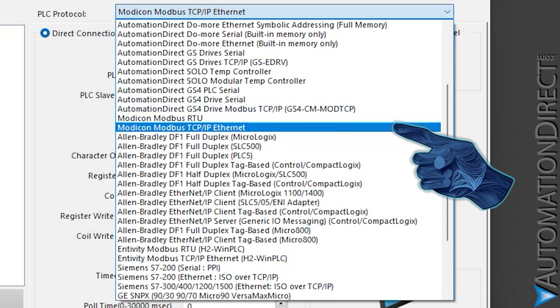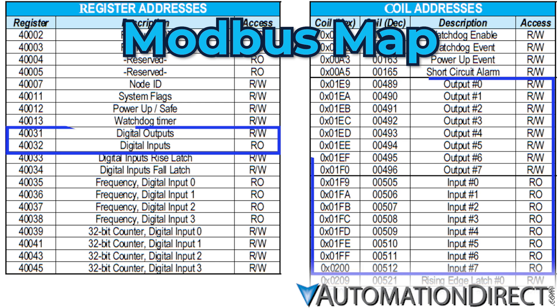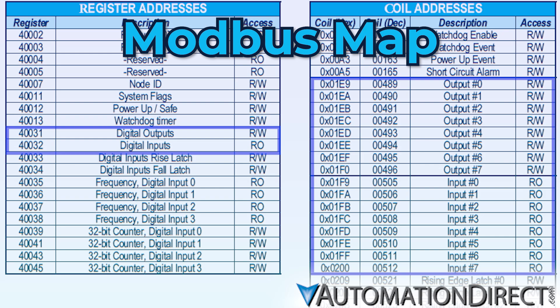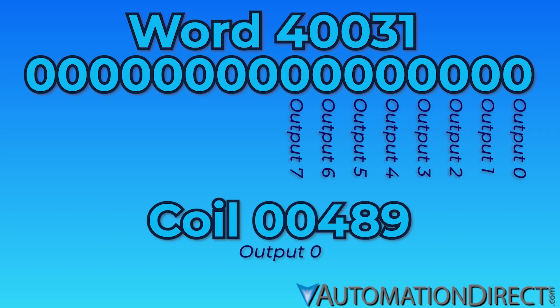Not to worry — in cases like this, we'll pick a more generic Modbus driver. We're using Modbus TCP, so we'll use the Modicon Modbus TCP/IP Ethernet selection. First, we'll set up our tags with the help of the Modbus map mentioned earlier. The I/O points are available as either coils or single words — that is, the coils packed into a word. For example, bit 0 of word 40031 represents output 0, just as does coil 00489.